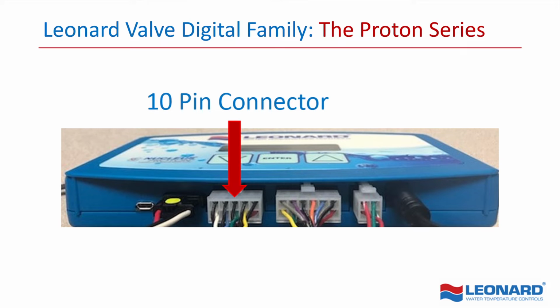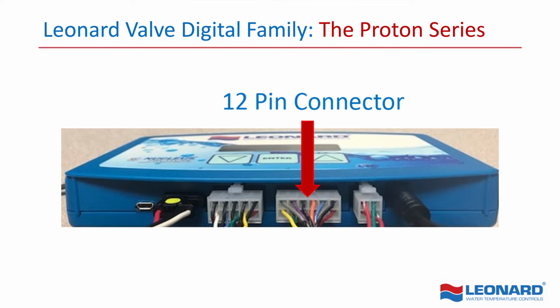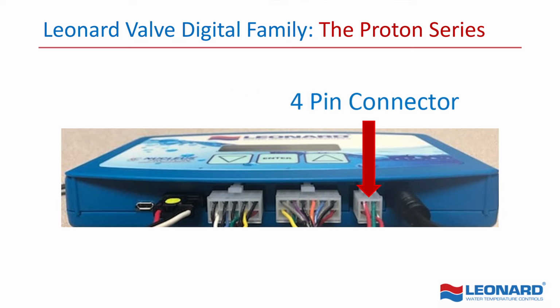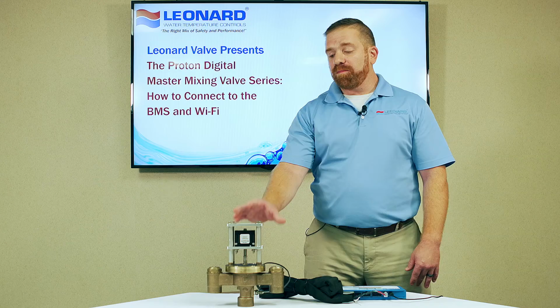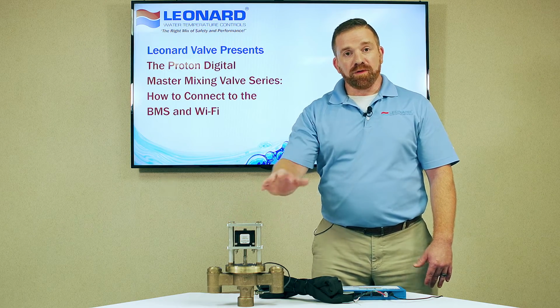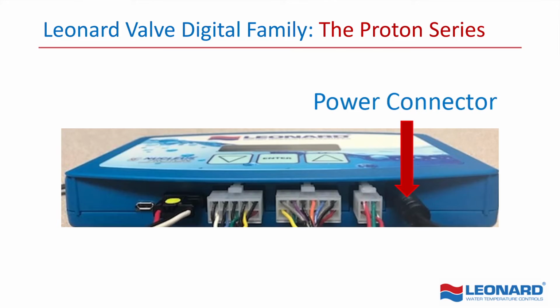Next after that is going to be your 10-pin connector, and that's going to be used for relay contacts for 5 different alarm conditions. After that is going to be your 12-pin connector for your BMS connection, either BACnet or Modbus. Next to that is going to be your 4-pin connector. That's going to be powering your motor. So you always want that to be plugged in as well. And finally is your barrel connector here on the very right, and that powers the control box itself.